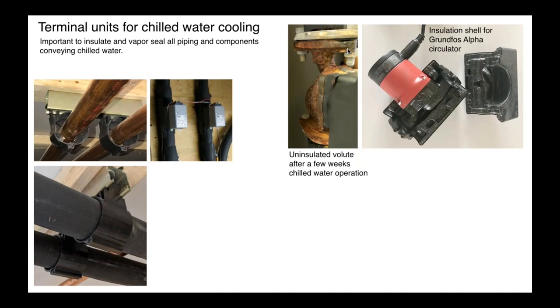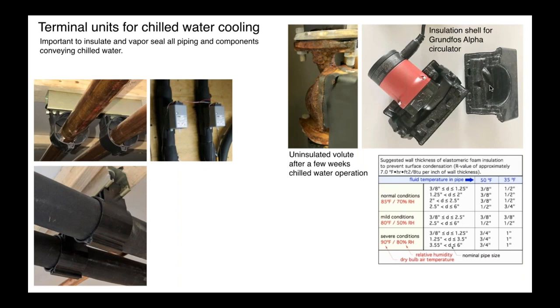It doesn't take long. So I know Grundfos, for one, there may be others, has an insulated shell for, in this case, the Alpha circulator. When you put that together, seal all the joints up with some silicone. The key idea is you don't want air that contains moisture to get to any surface that's below the dew point. So don't just push them together and say, I'm done. Seal it up good. Okay.